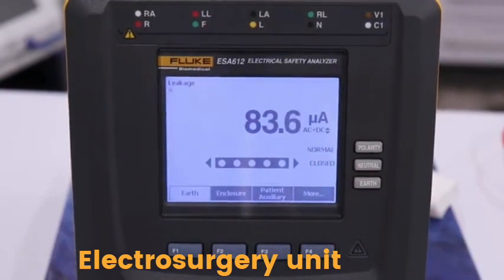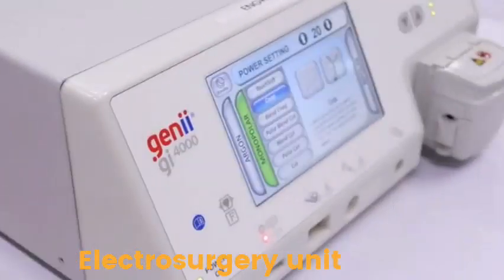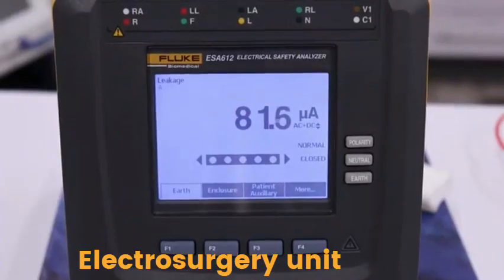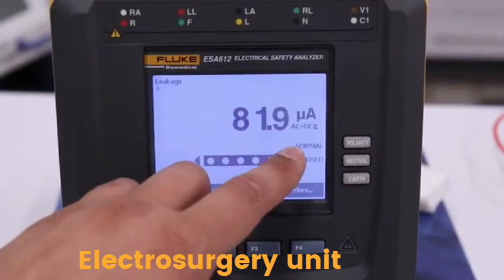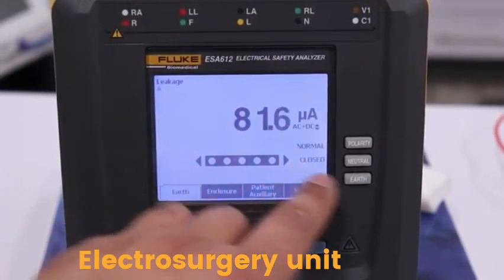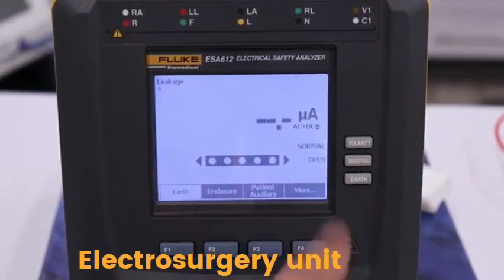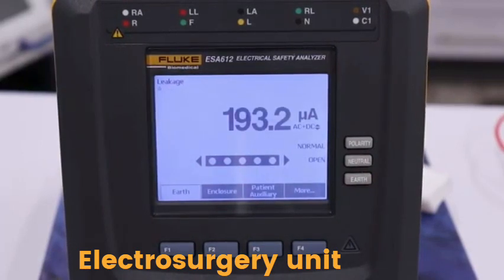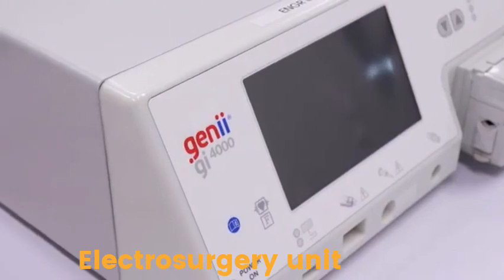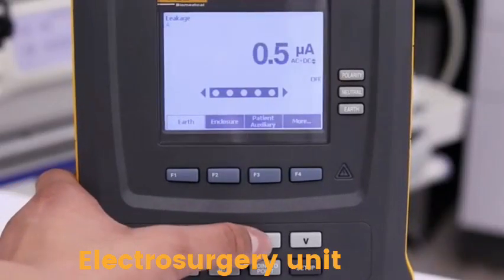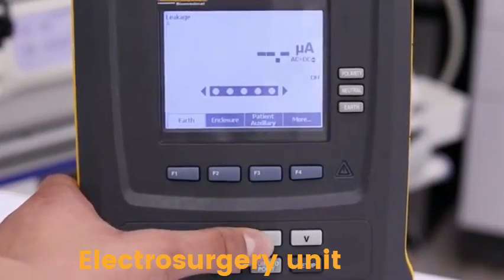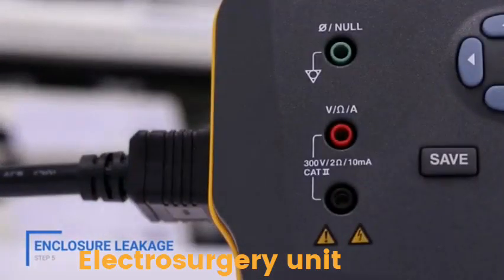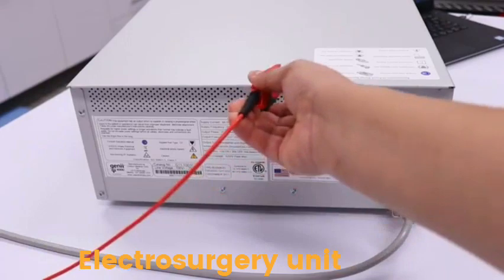The GI4000 will remain on in normal condition. To measure single fault condition, open the neutral line by pressing the neutral button. The GI4000 will turn off in single fault condition. Do not be alarmed. The GI4000 can be turned back on by pressing the A button on the ESA or by closing the neutral line. Enclosure leakage displays the current that would flow if a person came in contact with the housing of the device.